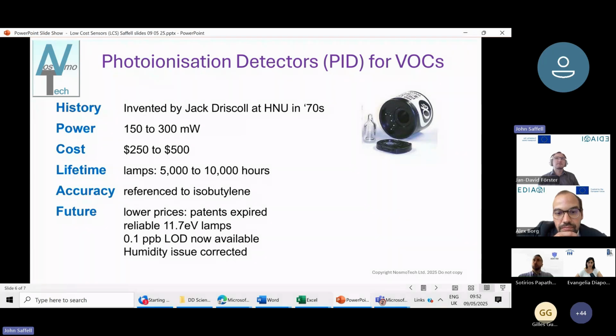The accuracy is kind of odd, because you calibrate with isobutylene when measuring a VOC, but in reality each VOC has its own constant, its bias or coefficient, whatever. So there isn't any universal way of getting the exact VOC you want. You get a generic VOC measurement with PIDs, but they do go down to subparts per billion now.